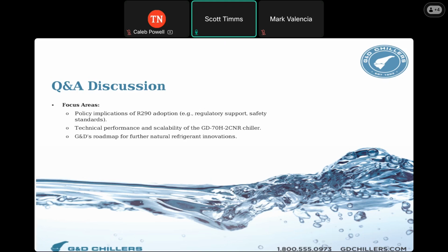And then just staying on top of your preventative maintenance. A lot of the time, if your condenser coil on your chiller gets dirty, that's going to cause the heat transfer efficiency of that condenser to go down considerably. Whenever that happens, you have higher condensing temperatures, so you're going to have more operating issues, and it also requires more power for the system to run at the same capacity. So keeping your condenser coil clean is another solid move.